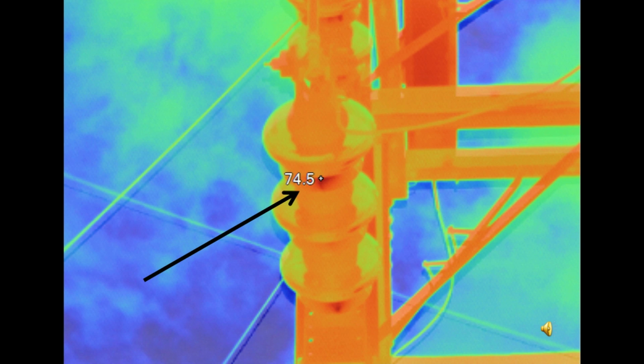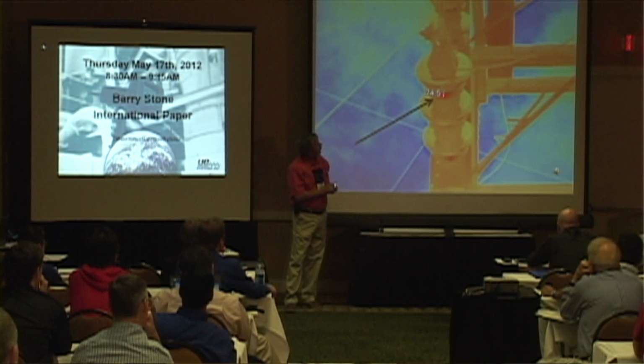This is the picture of the insulator I showed you, remember the one I took the digital picture of looking up under it? When I took that picture and came back with my IR camera, the little black spots we saw on the insulators were actually about 25 degrees hotter than the rest of the insulator. So what's that tell me? I'm standing there with my ultra probe and I can hear tracking happening. I can hear it, and I take my IR camera and I can see it too. It's neat to be able to hear and see, and that's what my IR camera allows me to do on these high voltage applications.